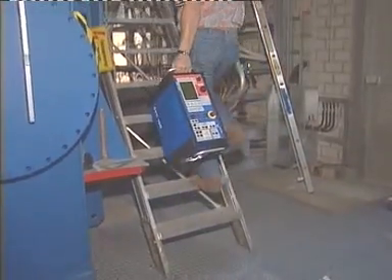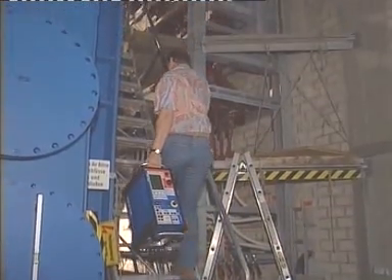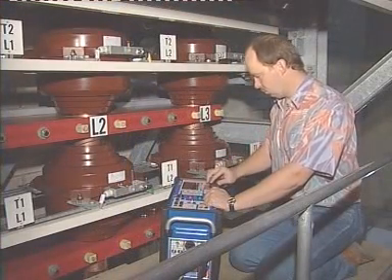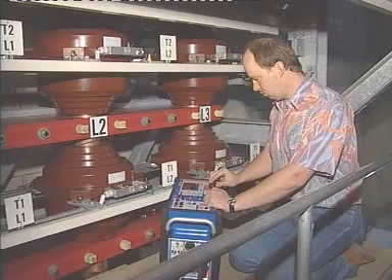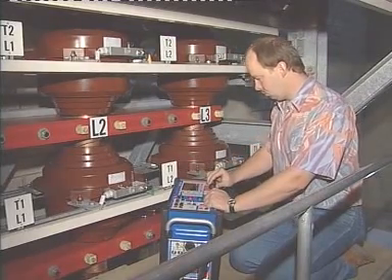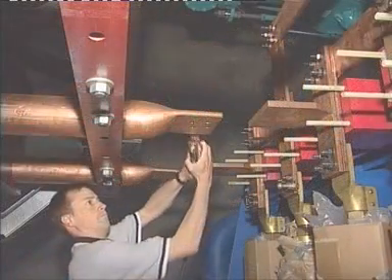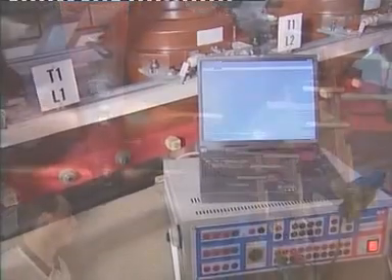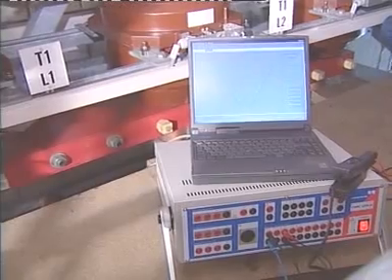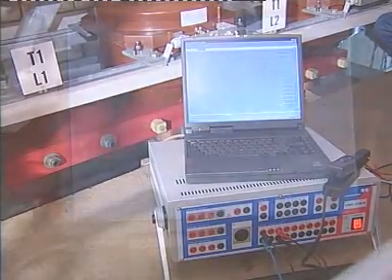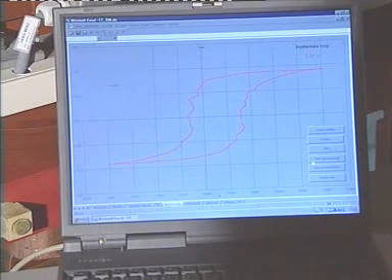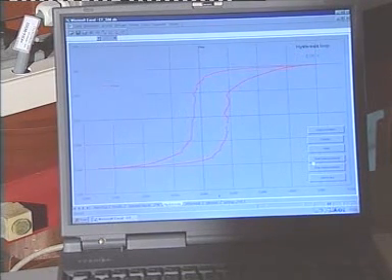The CPC100 contains a wide range of functions, such as measuring the CT and VT ratios, winding resistance, burden, magnetizing characteristic and contact resistance. All of this heavy-duty functionality is in a relatively lightweight package. Please note that the CT must not be open-circuited on the secondary side while these tests are carried out. With the relay test set CMC256 and a specifically developed software using the CMEngine interface, the hysteresis loop is oscillographed online.